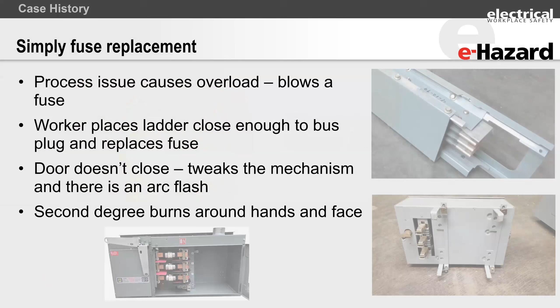The electrician put a ladder out, could barely reach over, changed the fuse, and tried to close the door of the bus plug. When the door didn't close, he tried to tweak this mechanism to make sure the door closes, and there was an arc flash, and he ended up with second-degree burns around his hands and his face.